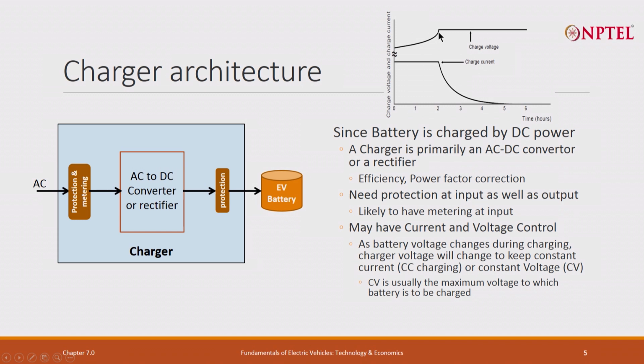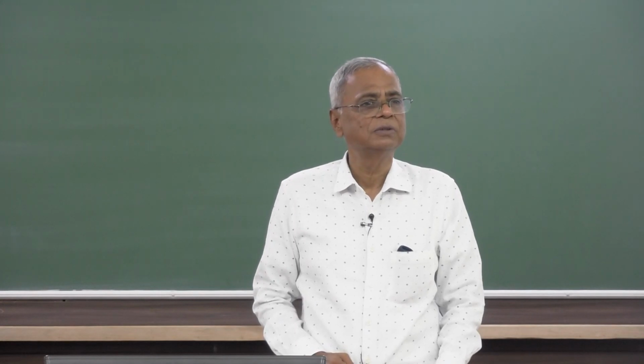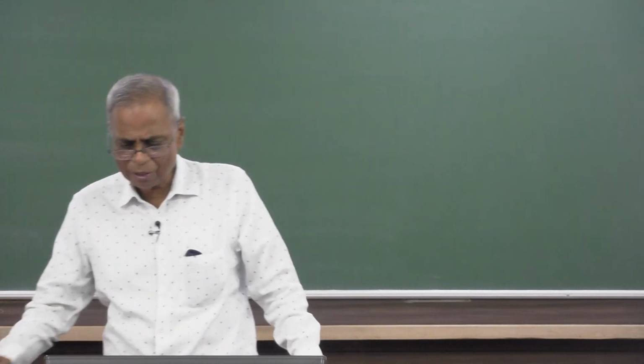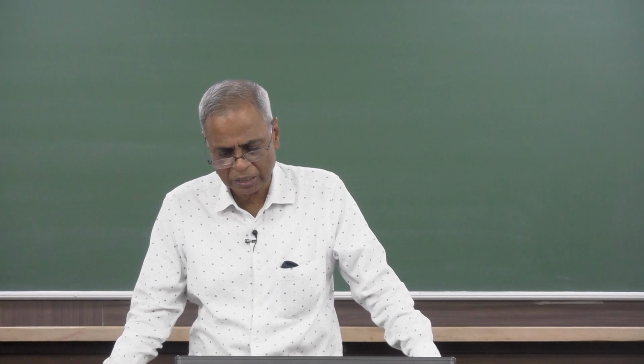When the battery is close to being full, the voltage has increased, then you do not charge using constant current. You actually clamp the voltage at the maximum voltage. If the battery's maximum voltage is 58 volts, I will clamp at 58 volts. And now I am doing very low rate charging, slower and slower charging.